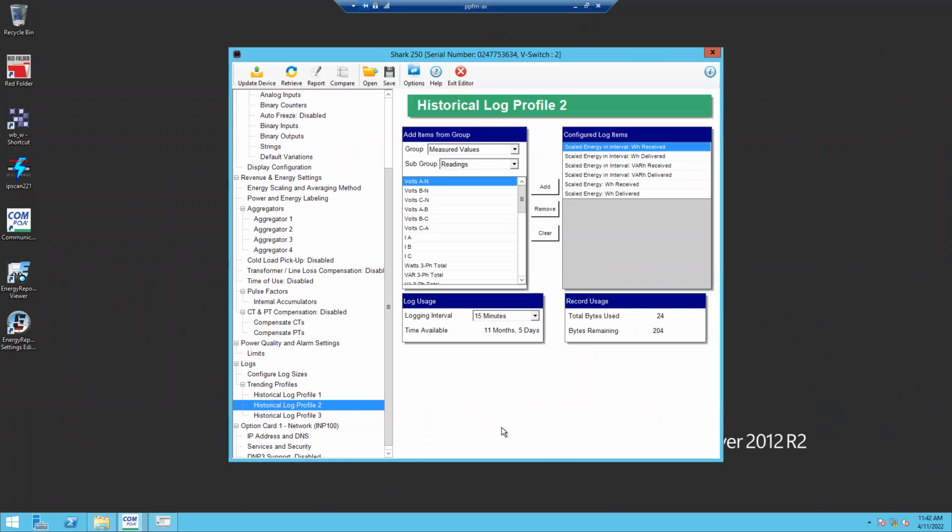So if you have solar or you have generators or battery backup, whatever, it'll tell you how much power is coming from the grid and how much is coming from whatever your other source is, because it can tell which way the power is going. It keeps track of those separately, so it adds them up separately. For example, with a solar building, as the day gets brighter and the solar comes online, there's a good chance the electricity coming in will fade off and the electricity going out will ramp up if it's creating more energy than the building uses.